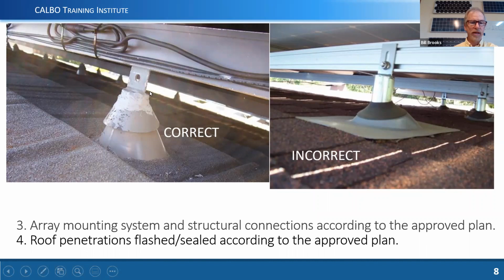Here on the left-hand side is a flashing that's specifically designed for that style of roofing, which happens to be a metal roofing. On the right, which is standard comp shingle, you can see that the flashing was not even installed. So we're dealing with a contractor here who doesn't know how to do flashings, and there's wires hanging down all over the place. They had the wrong clips on the rails. You had all kinds of problems in this installation. The one on the right was not installed by a contractor with qualified people. They hadn't trained their people.